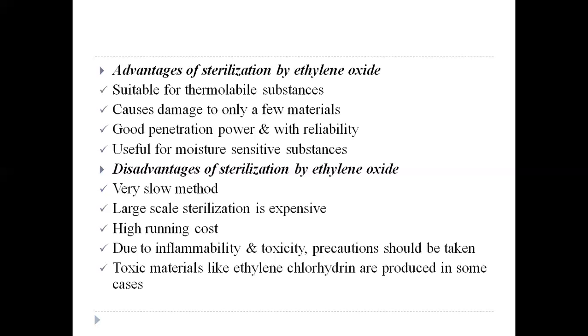The next one is its penetration power. Ethylene oxide, compared to other gaseous substances, has more penetration power. So depending on the penetration power, the sterilization of substances can be done even in their final packaging system. So that is definitely an advantage, and this method is also very reliable. We can rely on this method, that effective sterilization will be taking place.